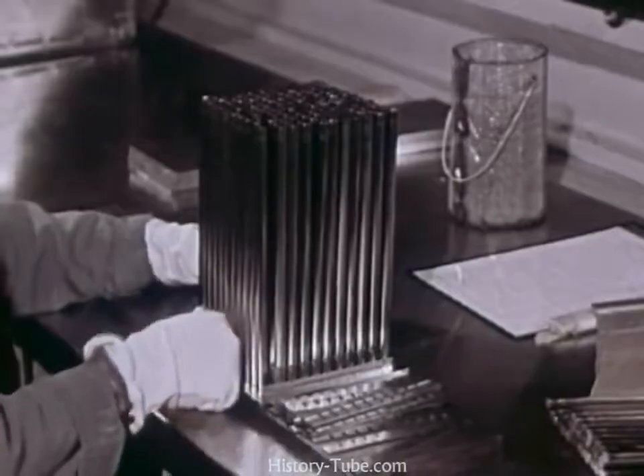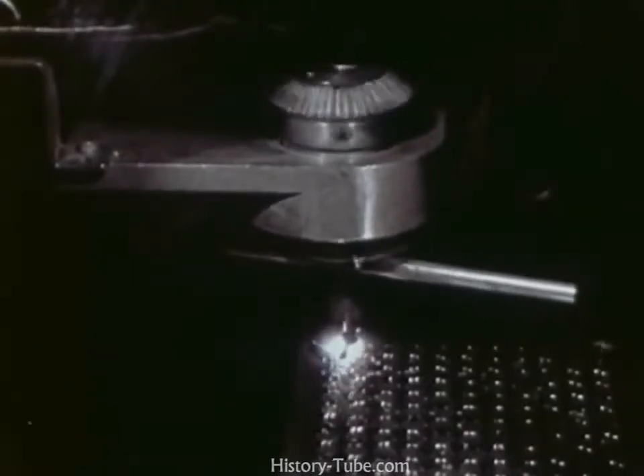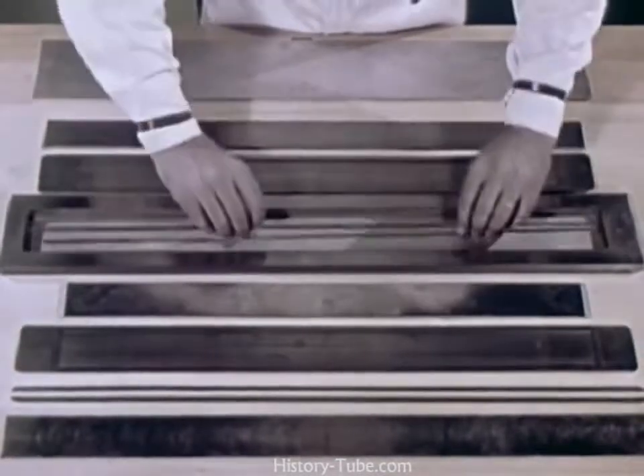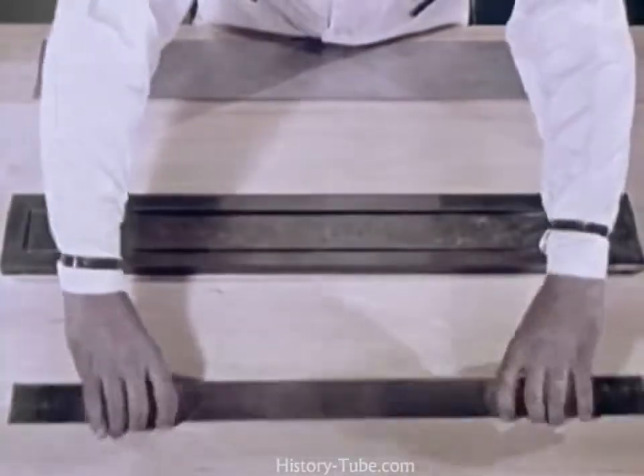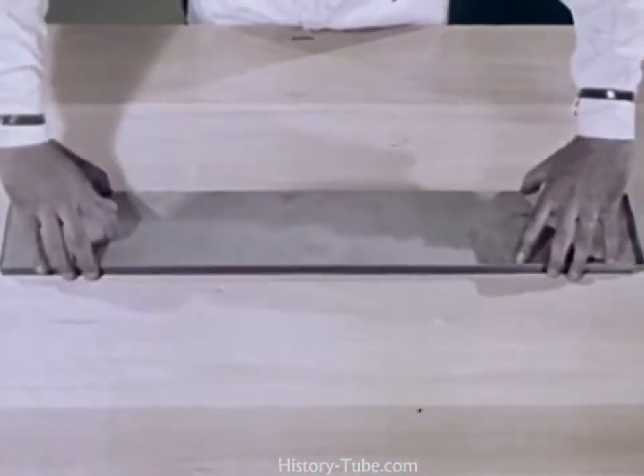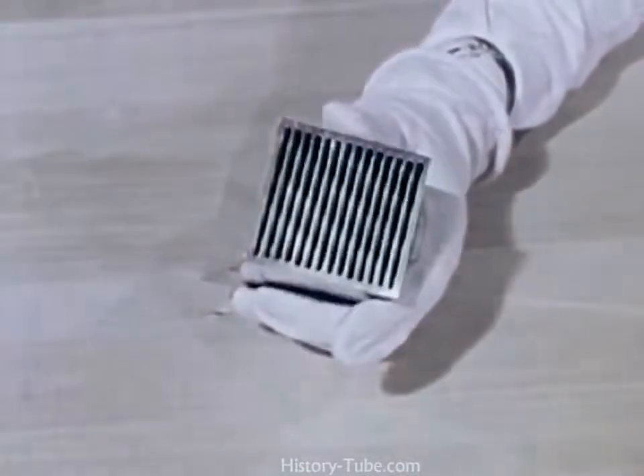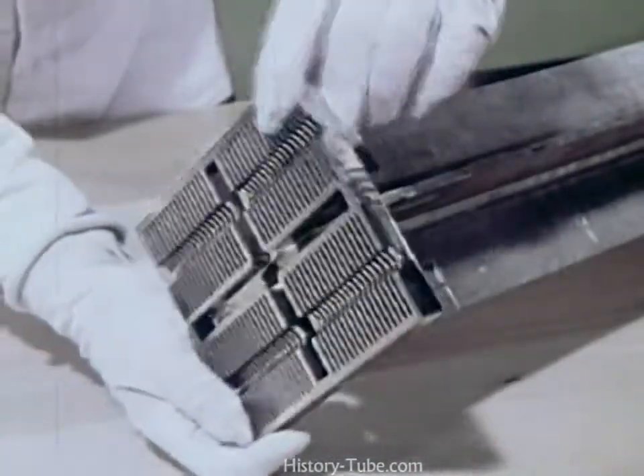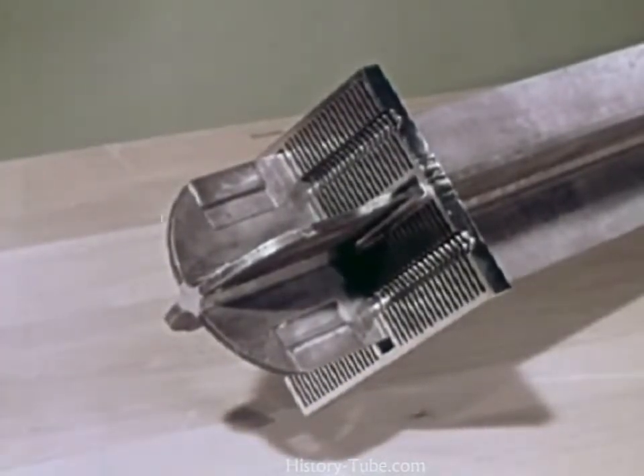Fuel rods and bundles were assembled, argon atmosphere welded, annealed, and machined. In the meantime, seed elements were also being made. The basic component of the seed cluster is an enriched uranium fuel plate. It is sandwiched between two zirconium alloy cover plates. Sub-assemblies were joined with the necessary spacers to create a cruciform channel for the control rod made of hafnium. Hafnium, being a good neutron absorber and having high corrosion resistance, is ideally suitable control rod material.